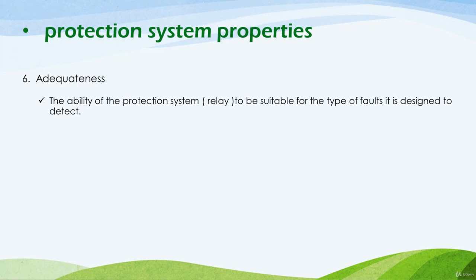Very good. Now the sixth property of the protection system is the adequateness, and the adequateness is the ability of the protection system in general, or the protection relay specially, to be suitable for its purpose, that is, what it will be put to protect. So we need the relay to be of the suitable type for the fault that it will detect. In some cases we need to detect the voltage fault in the circuit, so we will use an overvoltage relay. And in some other cases we need to detect the current fault, so we will use an overcurrent relay and it will be suitable for its purpose.